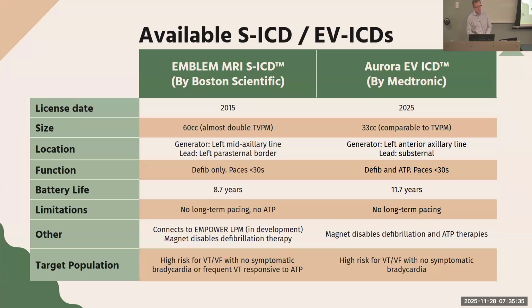So the Emblem was released in 2015. It has a very large generator, about double the size of a traditional pacemaker generator, and it only functions to defibrillate. It paces for about 30 seconds, but there's no long-term pacing. The battery lasts 7 to 8 years, and the magnet will disable anti-tachyarrhythmia therapy.